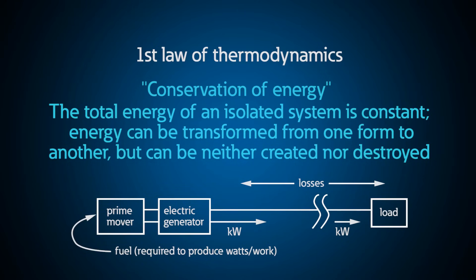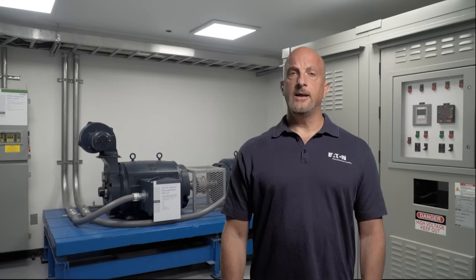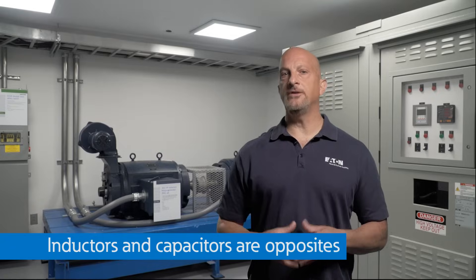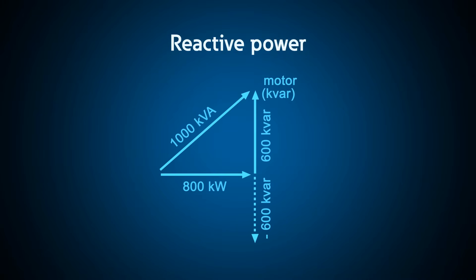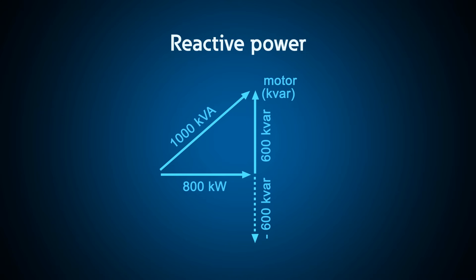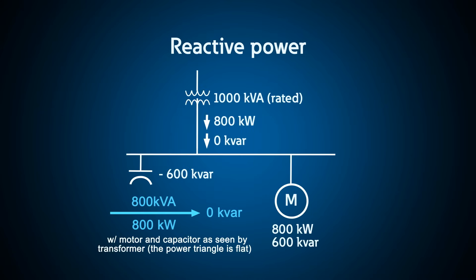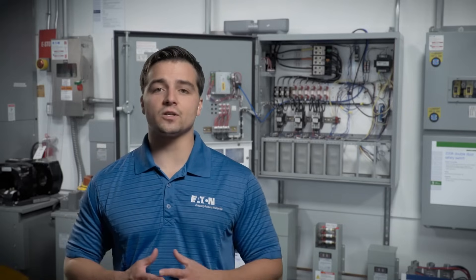Watts are real power and must be created by a source of power, like a generator. Energy in the form of mechanical power or fuel is used to maintain conservation of energy. Since magnetic or reactive power requires no energy to be created, we call it imaginary power. In electrical systems, the opposite of an inductor is a capacitor. To compensate for inductive load like a motor, a capacitor actually draws current 180 degrees out of phase and therefore is said to be a VAR generator and compensates for the VARs required by the motor. Now let's take a look at real measurements and see how VARs behave on power systems.